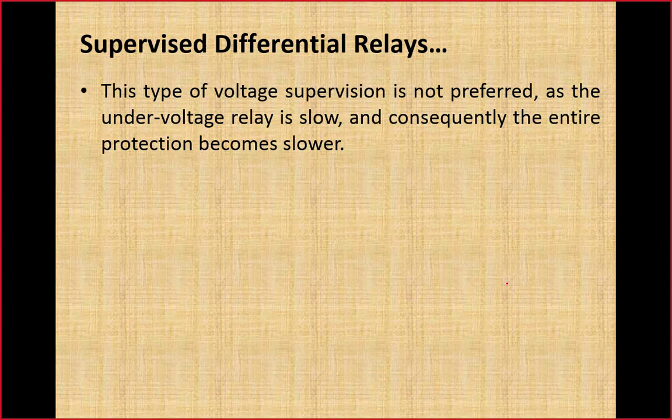So the problem with this type of supervision is that the operation of the undervoltage relay is too slow. It means the differential relay, although very sensitive and able to provide very quick protection, will have to wait for the undervoltage relay to operate first, and only then can the differential relay operate. Due to this, the overall protection scheme becomes slower, so it is not preferred.